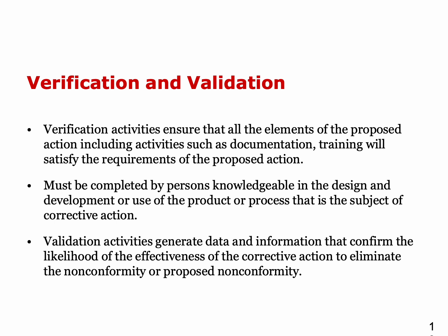Now, talking about verification and validation. Verification activities ensure that all the elements of the proposed action, including activities such as documentation and training, will satisfy the requirements of the proposed action. It must be completed by persons knowledgeable in the design and development or use of the product or process that is the subject of corrective actions.